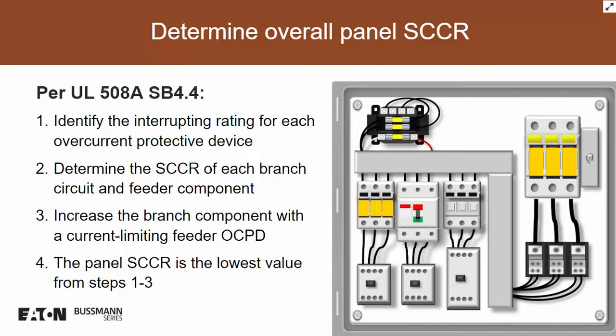Now let's move into step 3, because step 3 can sometimes boost up step number 2. Step number 3 is using, again, a current limiting feeder overcurrent protective device to boost up the branch components themselves and their SCCR rating. It's possible that step number 2 was based on a branch component that was only rated for 10 kA, and then step number 3, with a current limiting feeder device, can boost up that component that was 10,000, and push it up to 65,000 or 100,000. We just have to look at the charts and stuff like that. And then finally, whatever the lowest SCCR is that we find in the steps, that's where our SCCR is for our panel.